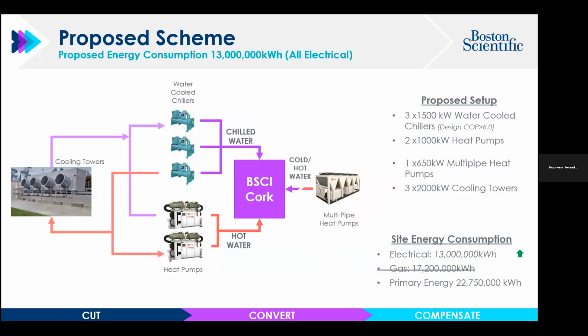This is still in design, we won't be doing this next year, we're still working on it. So when we say heat pumps, it's not really all about heat pumps. In this application, because of our heat load profile, which is predominantly clean rooms more than process applications, we're going to achieve it mostly through chillers with good heat recovery from the chillers. You see the red line coming down from the chillers to give you water to water on your heat pumps to provide your heat. The multi-pipe heat pumps on that side are really used for top up, so when environmental conditions are adverse, we may still need to top up that balanced system.